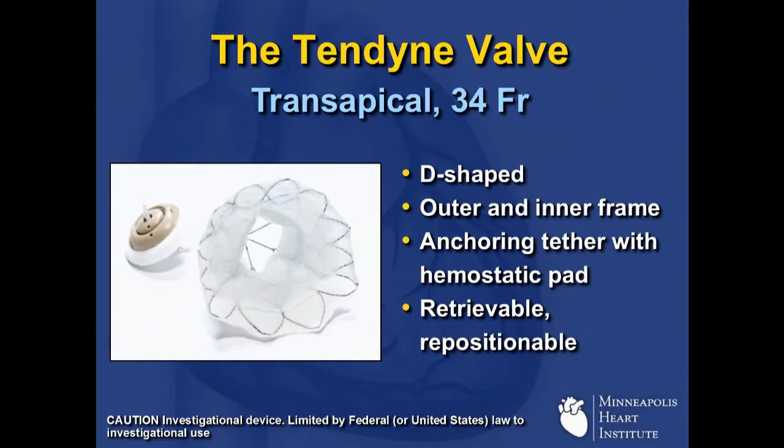As many of you know, the Tendyne valve is a trans-apical 34 French system. It's anatomically shaped — D-shaped in configuration. Like a lot of these valves, it's got an outer and inner frame. The anchoring mechanism is a tether, which is connected to a hemostatic pad that sits on the epicardial surface of the heart, which not only anchors the valve in place but also serves as a hemostatic pad. Importantly, the Tendyne valve is completely retrievable and repositionable all the way up until the time that you cut that final tether and leave it in the patient.